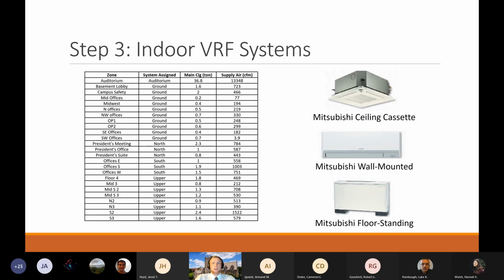So the third step was to size the indoor VRF units. These are the units inside the building which distribute the air to the rooms. Instead of using the system's checksum report, we actually had to use the zone checksums report and look at the supply air CFM and the cooling load for each of those individual zones of the building. The indoor units could not be more than 4 tons each. So some of the zones, such as the auditorium, needed multiple indoor units.